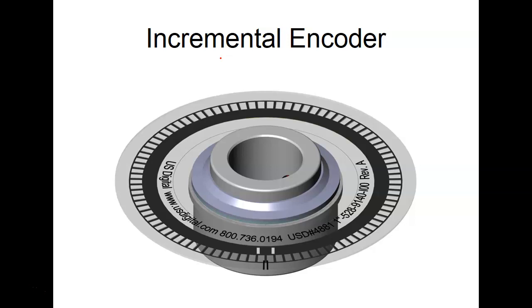Back it up or use a battery on the counters. So this is what your robot uses. I don't know if they showed y'all that when you took the operation and programming, but on the side or in the back of every robot is a set of batteries that keeps those counters, right? You understand that for us. But if you ever lose batteries on robots with the power off, then you're going to lose what we call the origin, the zero reference from the robot.